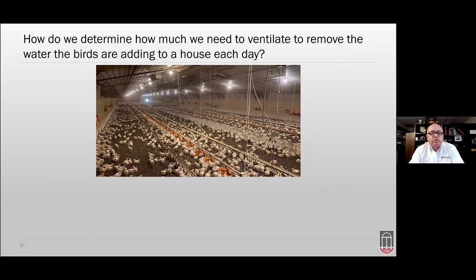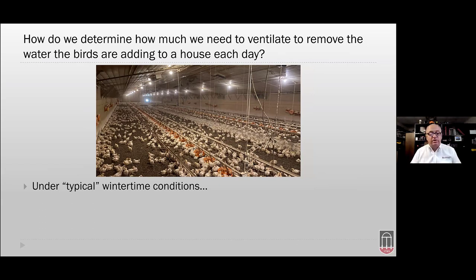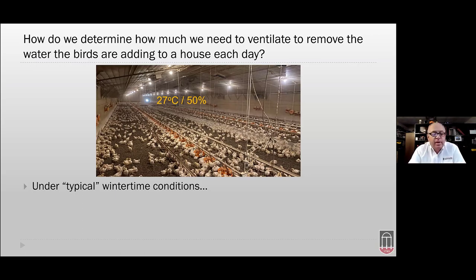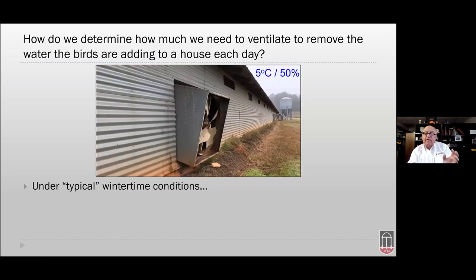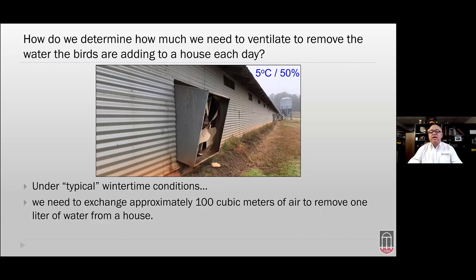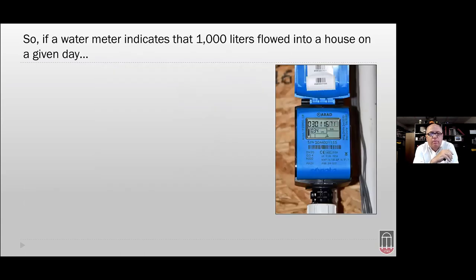How do we determine how much we need to ventilate to remove the water the birds add each day? Under typical wintertime conditions — and that's always the dangerous one — with 27°C inside at 50% humidity and about 5°C outside at 50% humidity as average over the course of the flock, we need to exchange approximately 100 cubic meters of air to remove one liter of water from a house.